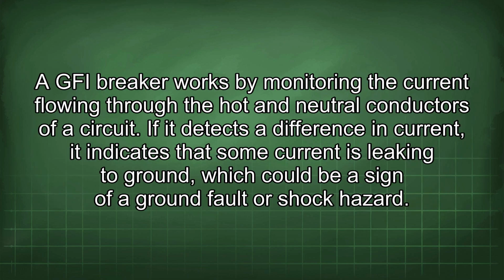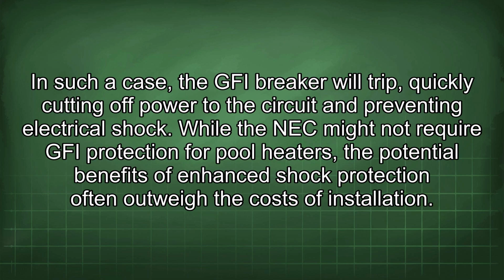A GFI breaker works by monitoring the current flowing through the hot and neutral conductors of the circuit. If it detects a difference in current, it indicates that some current is leaking to ground, which could be a sign of a ground fault or shock hazard. In such a case, the GFI breaker will trip, quickly cutting off power to the circuit and preventing electrical shock.